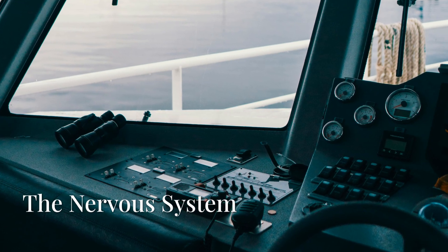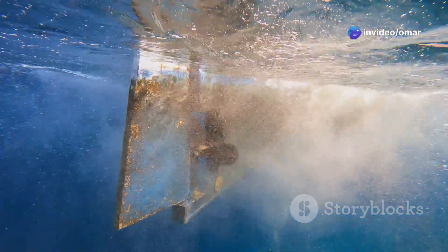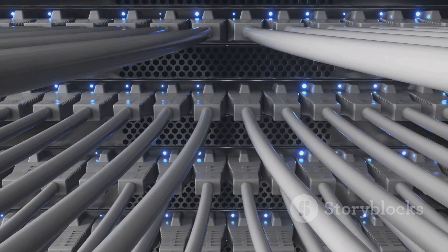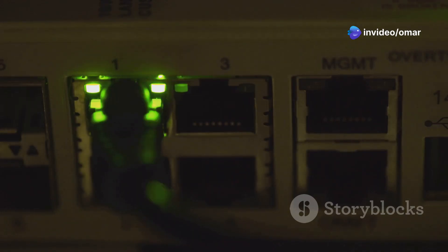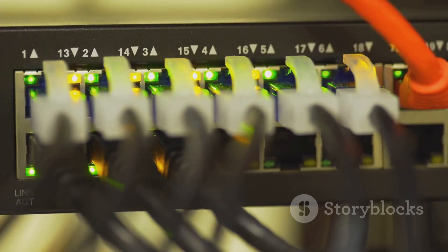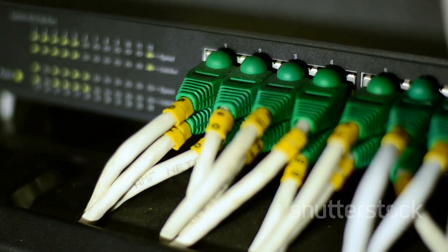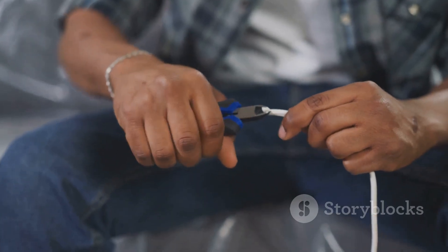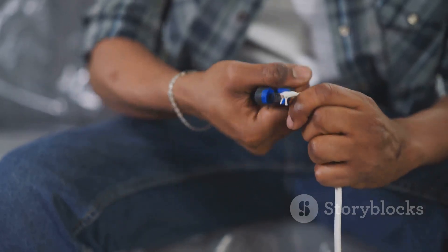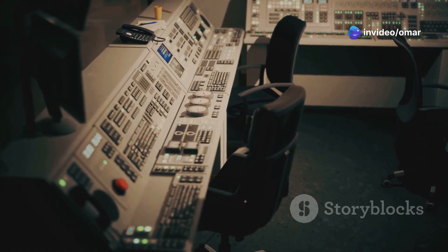All these components scattered across a giant steel ship — computers on the bridge, sensors on the mast, thrusters deep underwater — need to talk to each other instantly and reliably. They're connected by the DP network, the vessel's central nervous system. This isn't like the Wi-Fi in your house — it's a high-speed, industrial-grade, redundant data network made up of at least two, often three, completely separate physical networks with independent ethernet switches and cables running through different paths in the ship. If one network goes down, all data simply continues to flow on the other without any interruption.